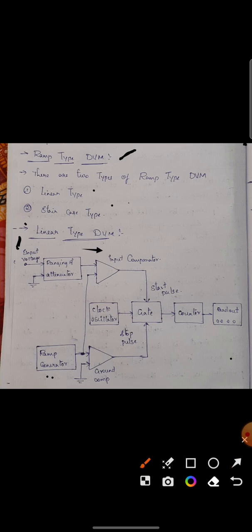Here, the input comparator has two signals. One is from the ranging and attenuator, that is from input voltage, and another one is from the ramp generator. It produces the ramp signal. So it contains two signals: one from input voltage and another from ramp generator.